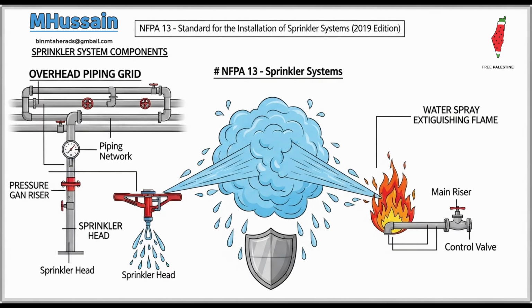It's just astounding when you step back and see how specific the compliance details become. I mean, from the acceptable leakage rate during a hydrostatic test, measured in ounces, to the structural limits that define an obstructed versus unobstructed space, right down to that 7.5-foot mark. We've really seen today that NFPA 13 demands a truly deep dive into prescriptive, often numerical data. It covers everything from complex commodity classification, thinking about Group A expanded plastics or those laced tires, all the way to critical structural geometry, like needing 4-way seismic bracing on risers.